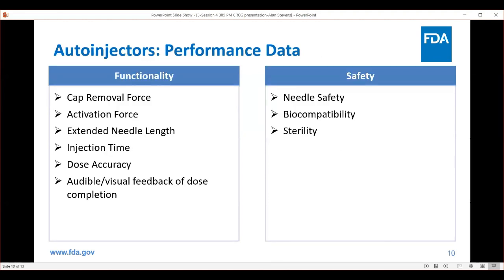For auto-injectors, I'm listing the cap removal force, activation force, extended needle length, injection time, dose accuracy, and then any feedback mechanisms on dose completion as key considerations to look at. And then very similar needle safety, biocomp, and sterility. Again, the auto-injector is generally not part of the container closure, primary container closure system.